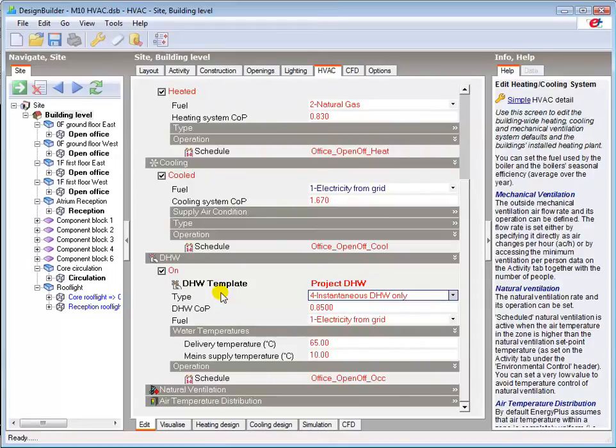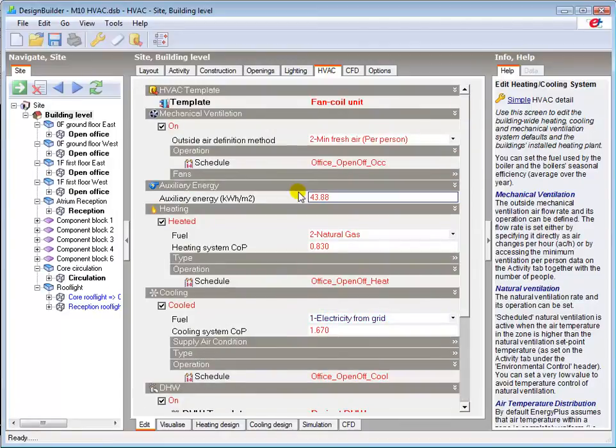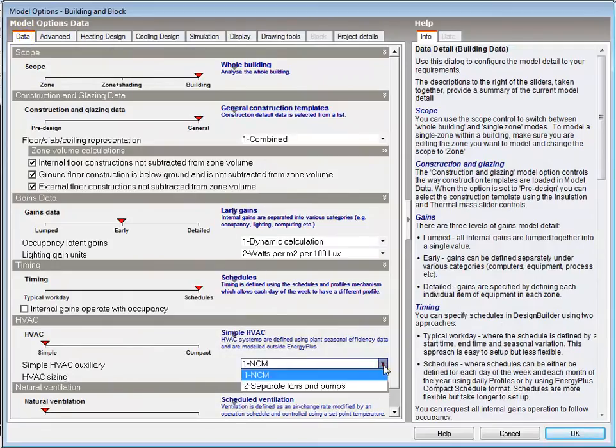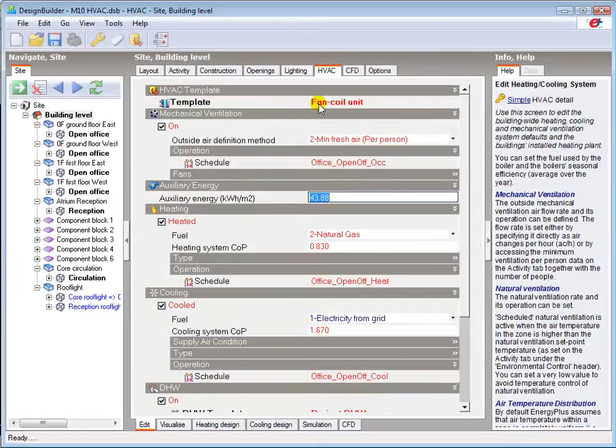The template loads the default operating parameters for the heating and cooling systems, such as the fuel type and coefficient of performance. And it will automatically set the auxiliary energy consumption of fans and pumps. An alternative auxiliary energy definition method is to use the separate fans and pumps option in model options here. In many cases, this will be preferable.